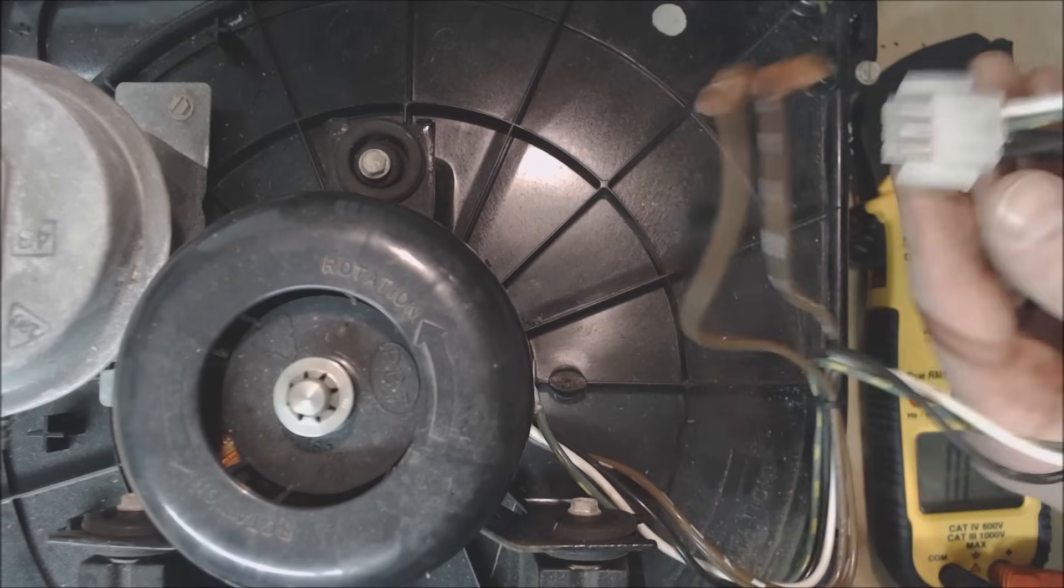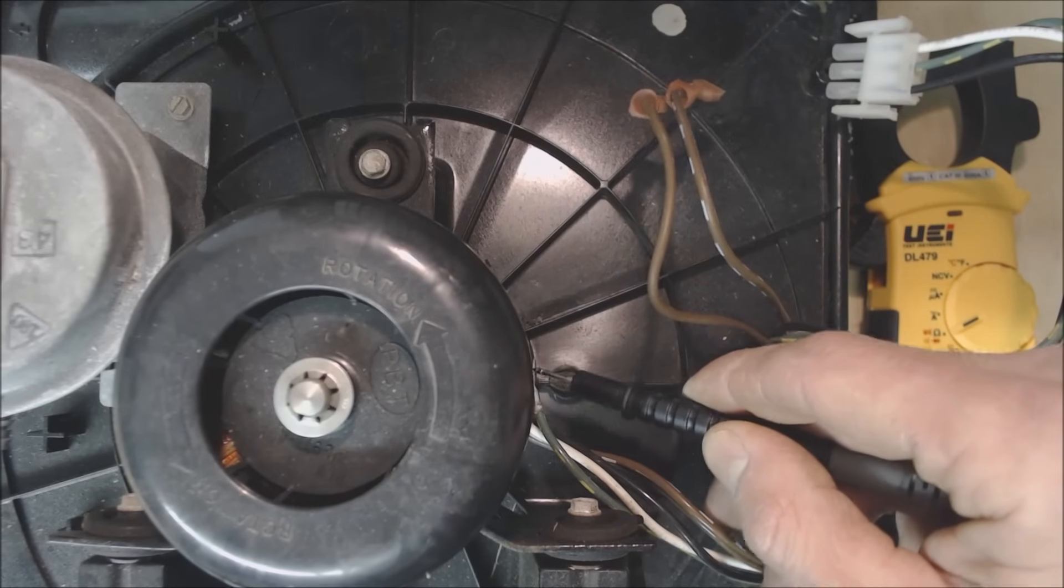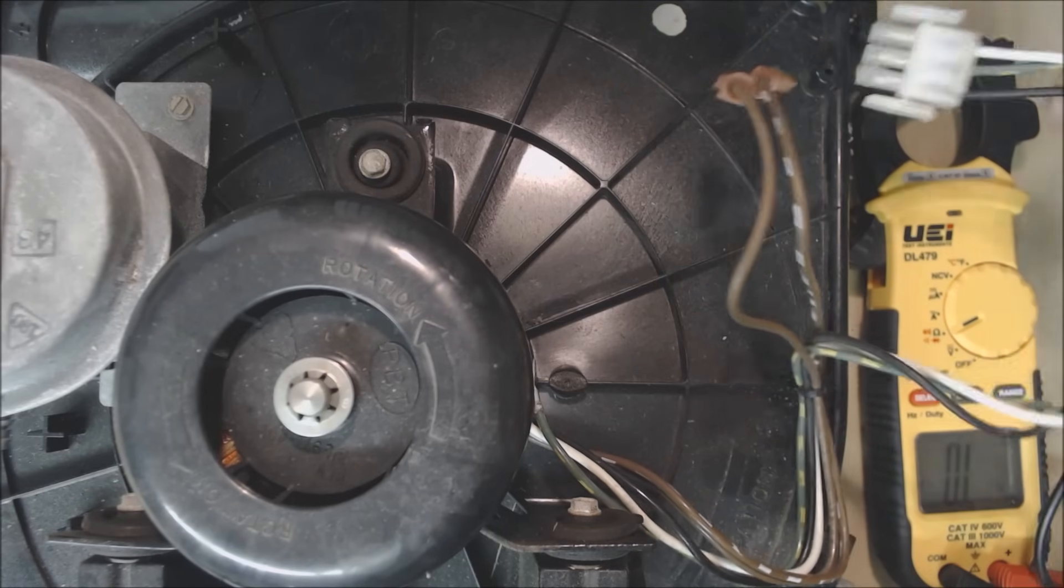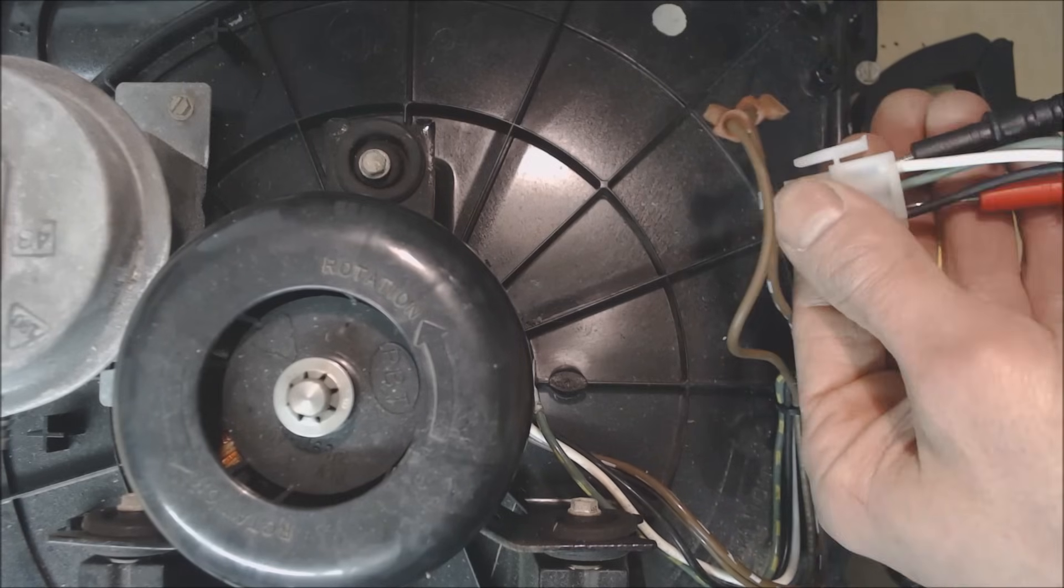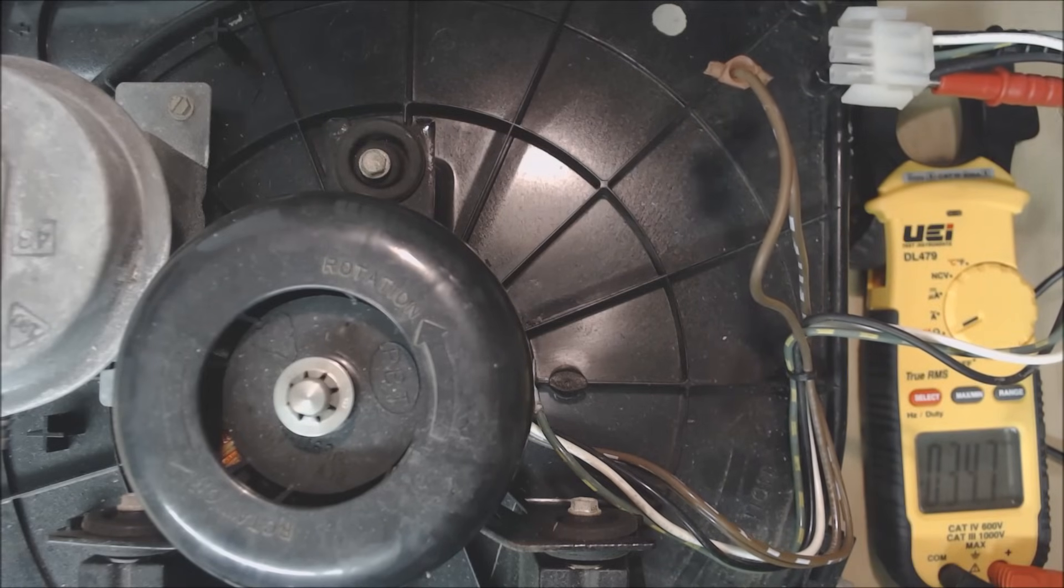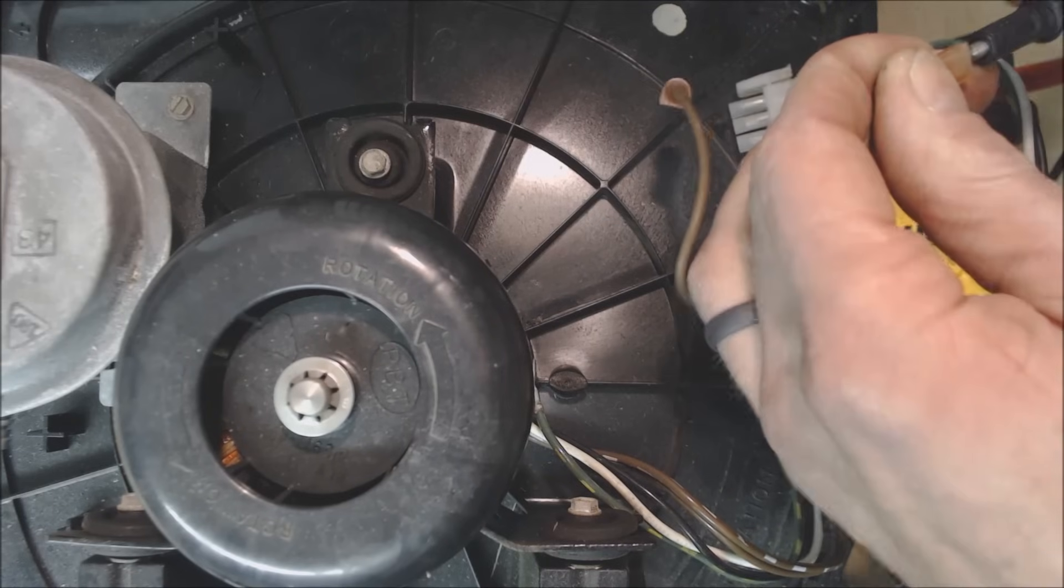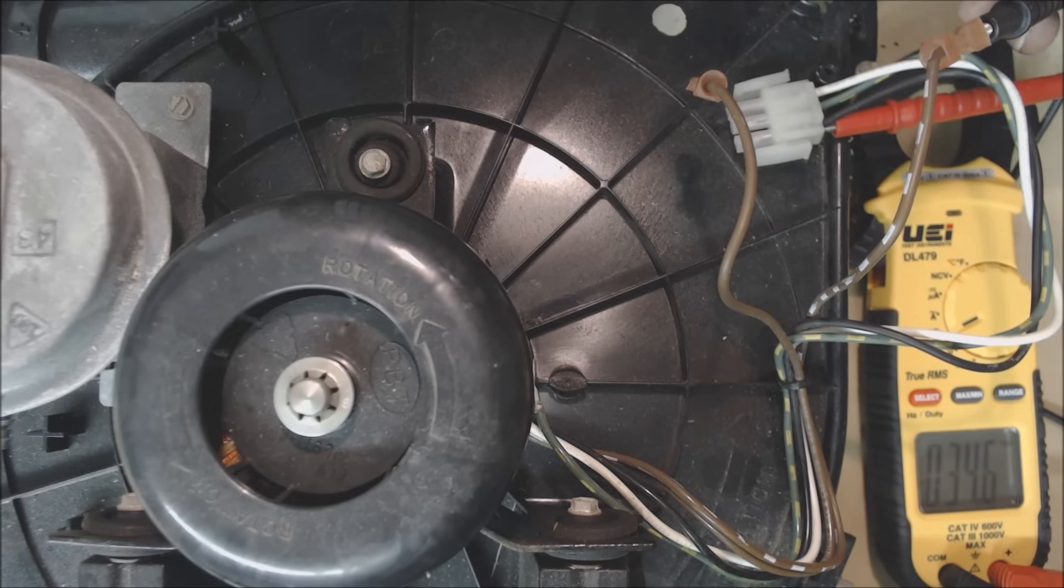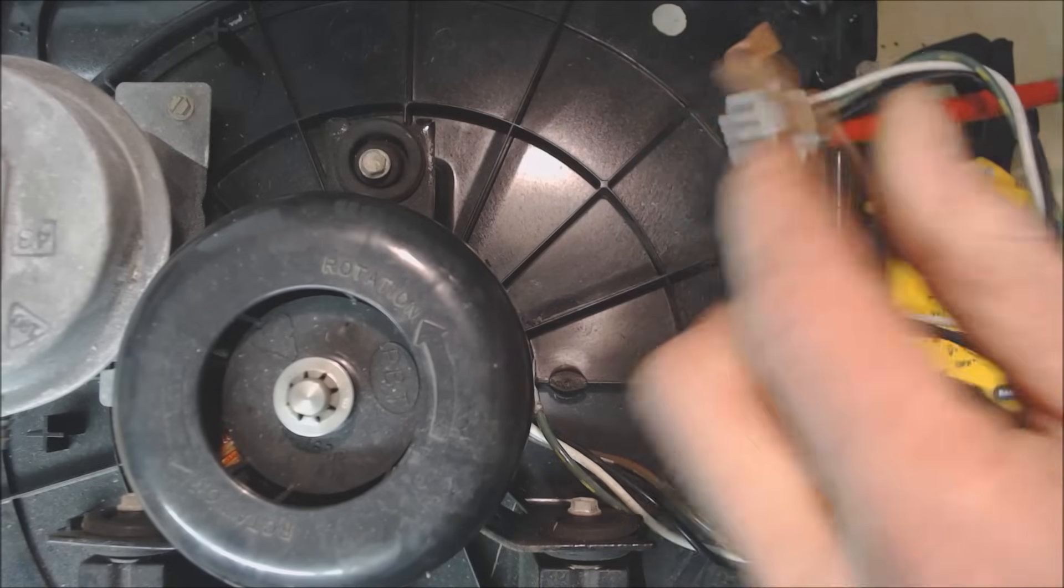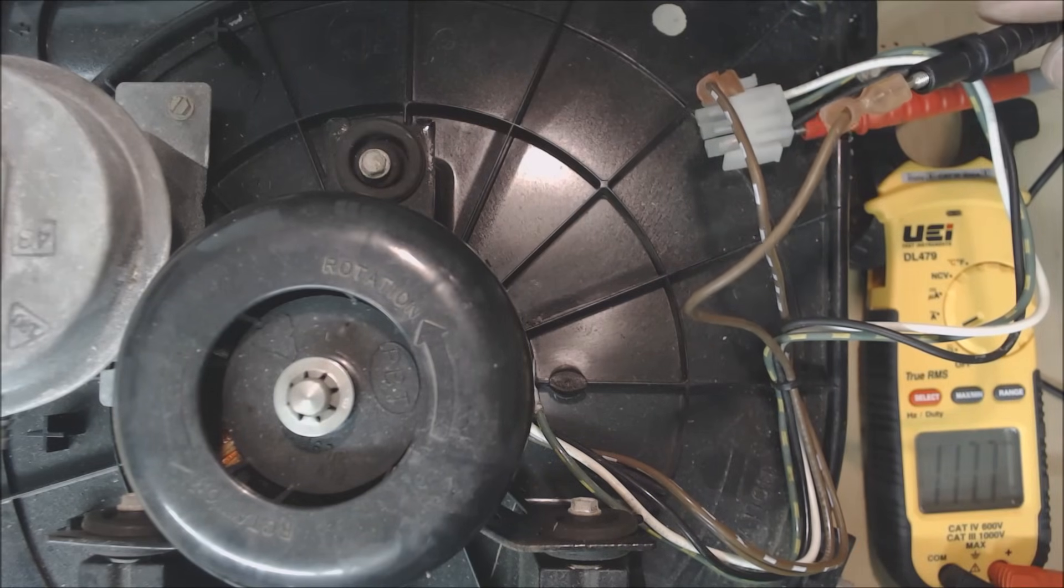The next test that we'll do is we'll just check the windings and we'll go from common to hot. And you see that we have 34 ohms of resistance. We'll get the same reading if we go from hot to this capacitor wire with the white on it. Should have about 34 ohms of resistance. The other one said 34.7, this one says 34.6 ohms. And now we'll go ahead and check from hot to the other capacitor wire. And you see that we're reading 117 ohms.